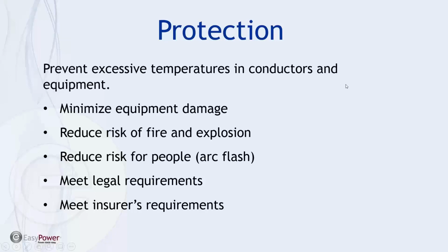So the purpose of protection is to prevent damage to the equipment, and this is caused by temperatures either in the conductors themselves or to the equipment. And so we're trying to minimize equipment damage, potentially reduce the risk of fire and explosion in the equipment or the facility where people may be in the area. There's also a potential need to meet legal requirements, especially in safety backup systems or emergency equipment. And then oftentimes there will be a benefit in meeting insurers' requirements for protection of the facility itself.